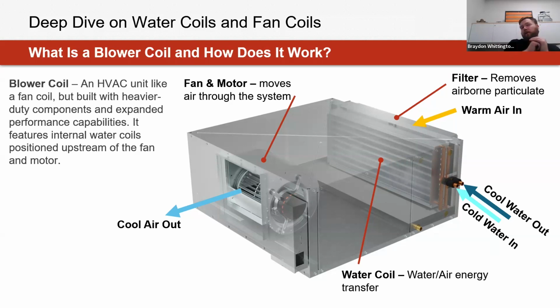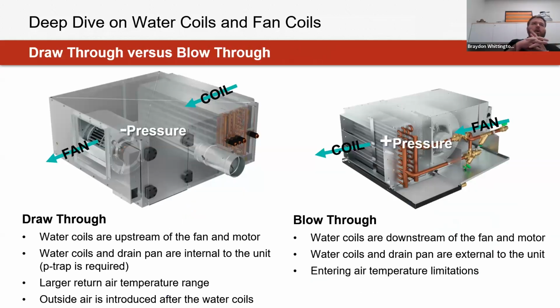But a key characteristic or difference between the two is the amount of static pressure these fans are really working against. Blower coils handle higher tonnage and higher airflows within the system, and more commonly than not, especially when looking at fan coils specifically, these deal with lower static applications. I've seen some of you mention single zone applications, so anywhere from a negligible amount up to a quarter inch of static in terms of what it would really be handling.